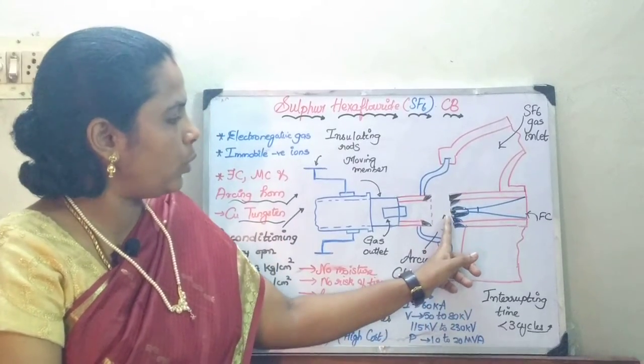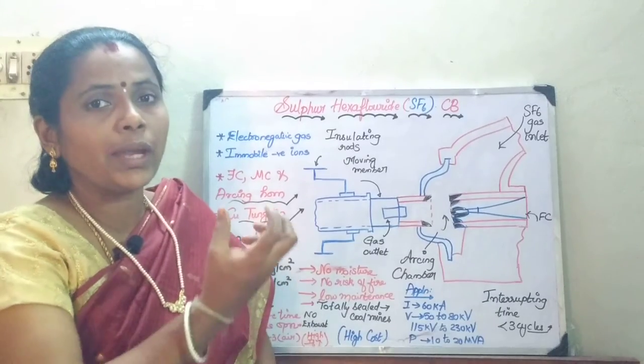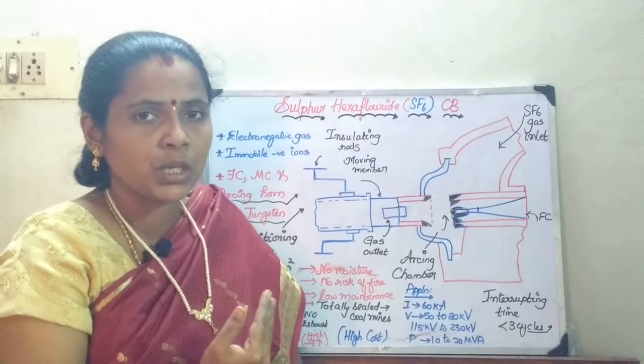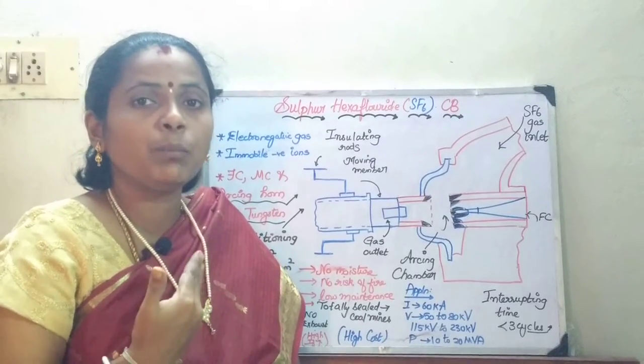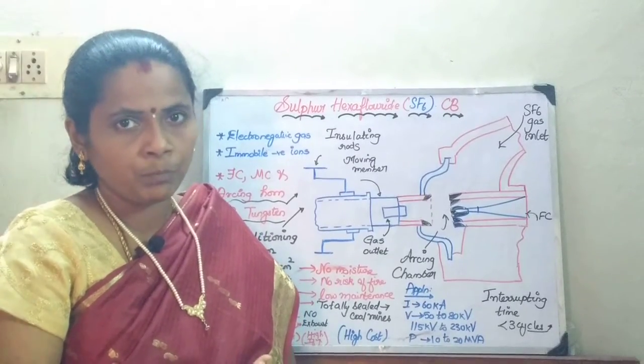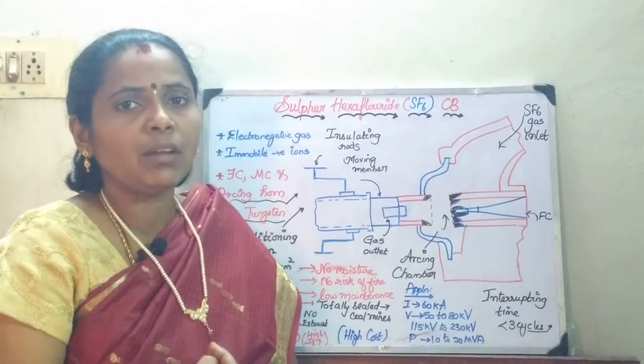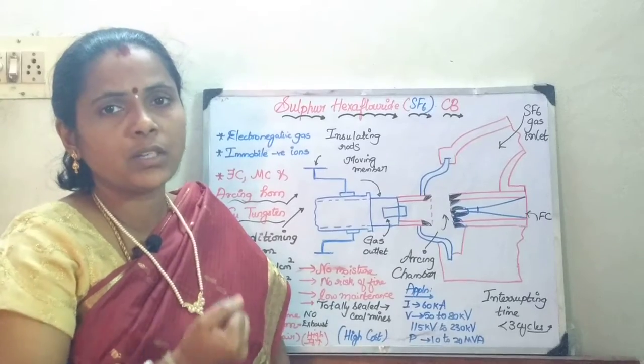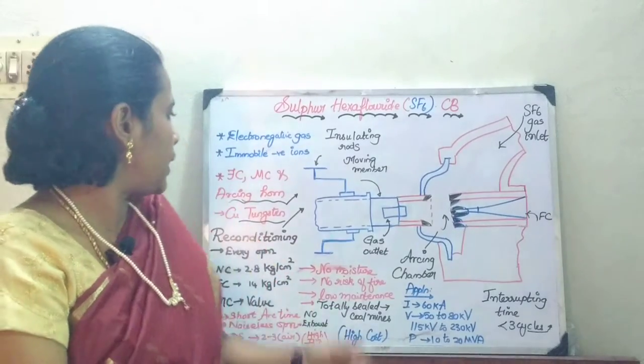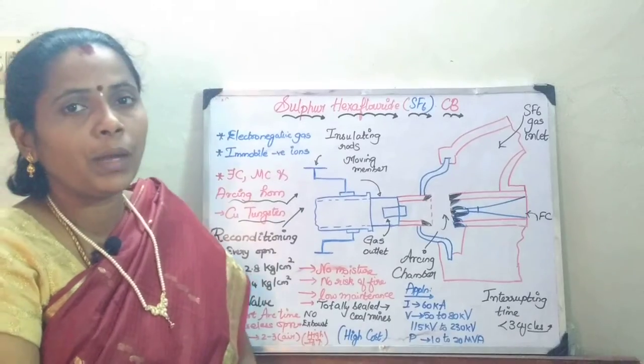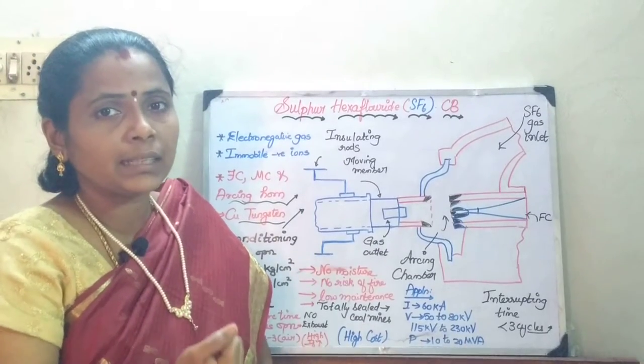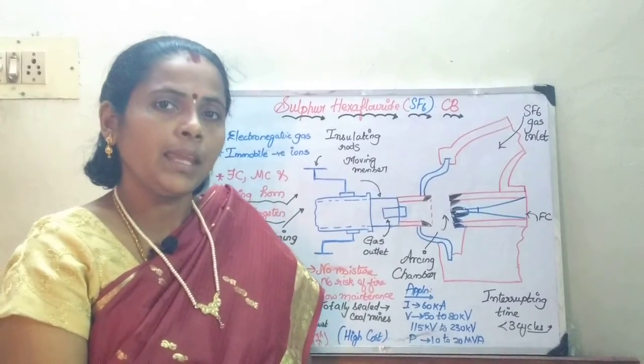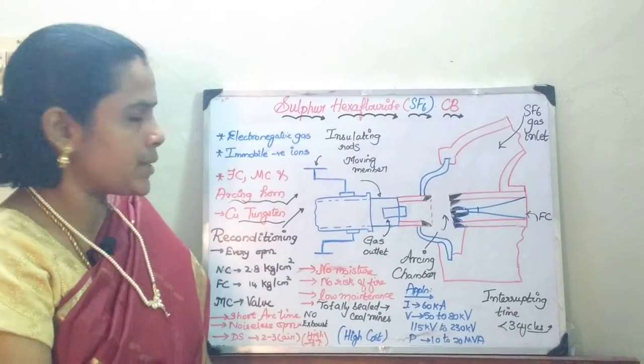Whenever this SF6 gas is allowed to flow through, it absorbs all the electrons, thereby providing deionization — in other words, it improves the dielectric strength. The arc is going to quench at a very faster rate. It absorbs all the electrons and converts them to immobile negative ions. Whenever it converts them into immobile negative ions, the conducting path gets reduced and as a result the arc is quenched at an easier and faster rate.